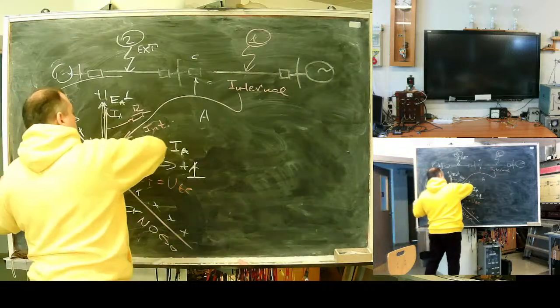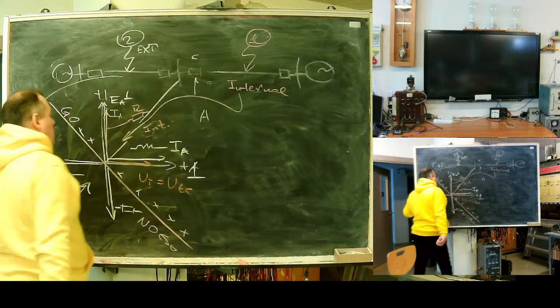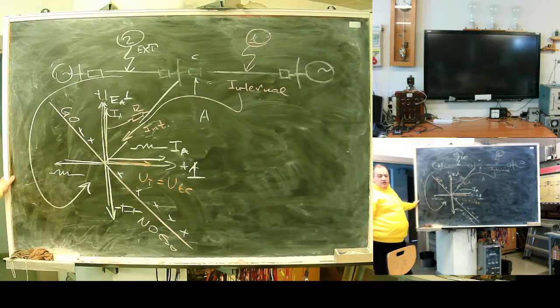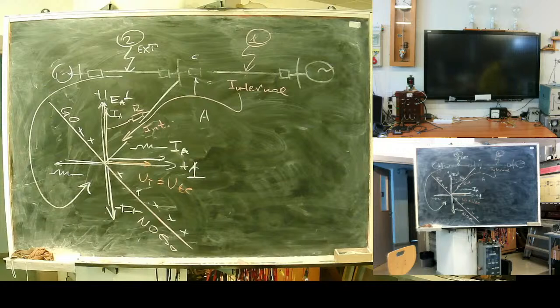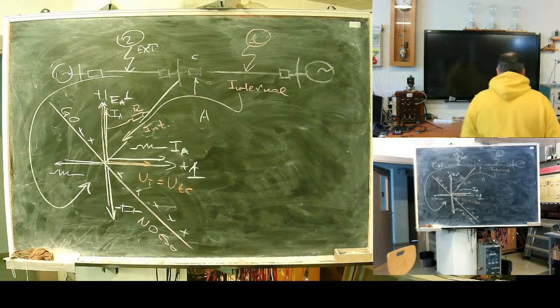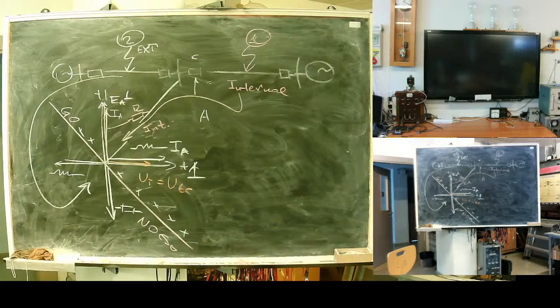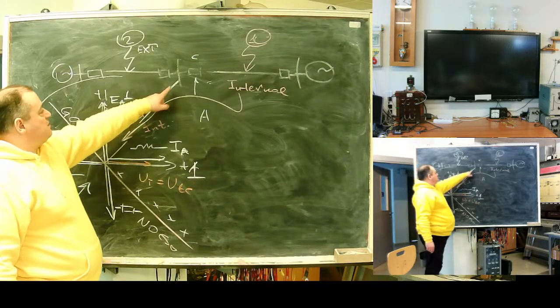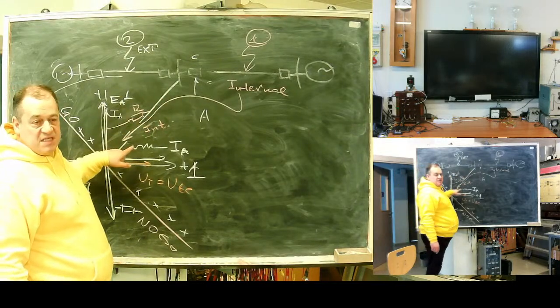The idea is, for electromechanical relays, there was the idea of maximum sensitivity, at which angle minimum power is required for the relay to trip. This is the vector of maximum sensitivity.